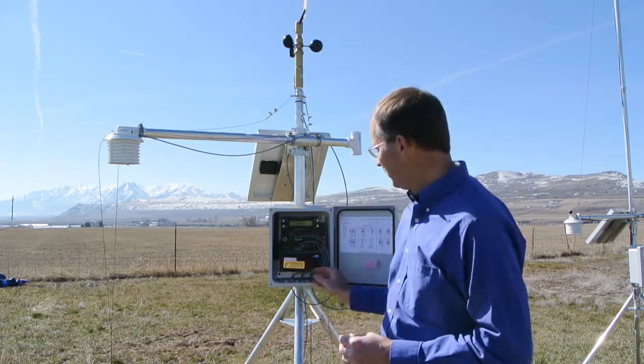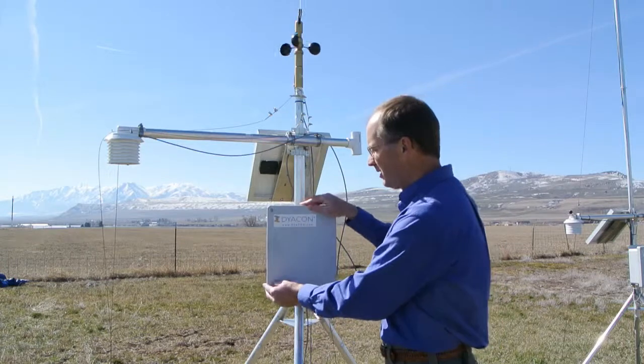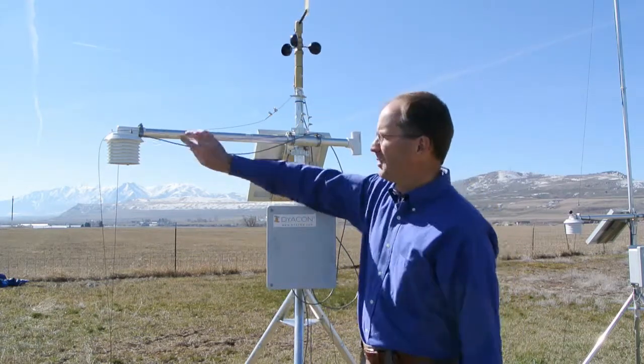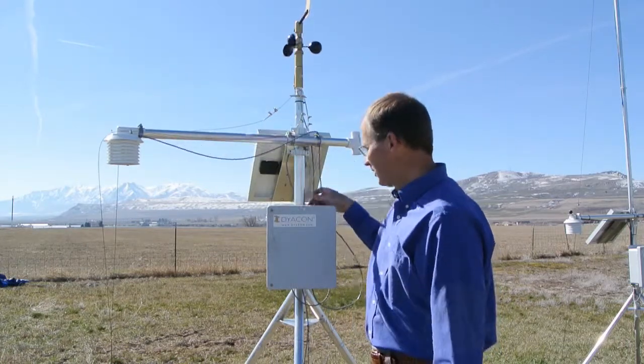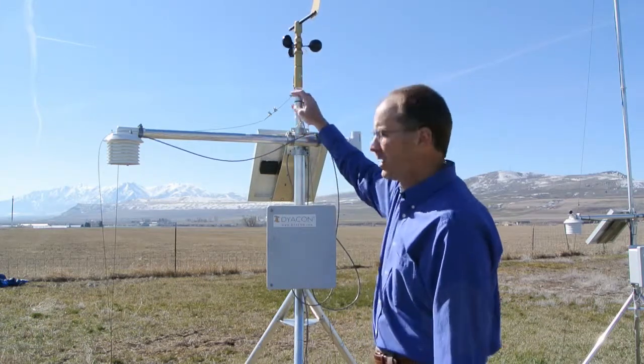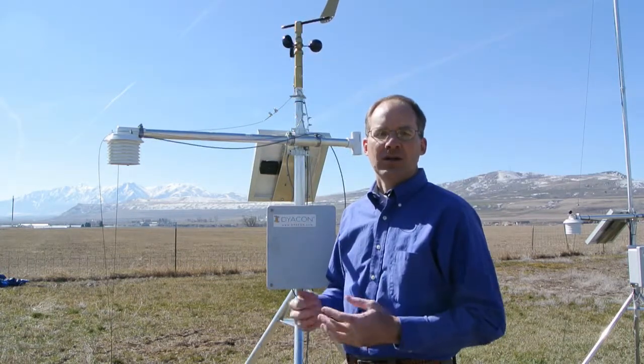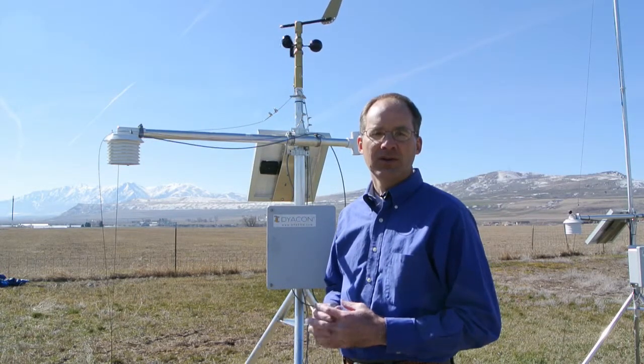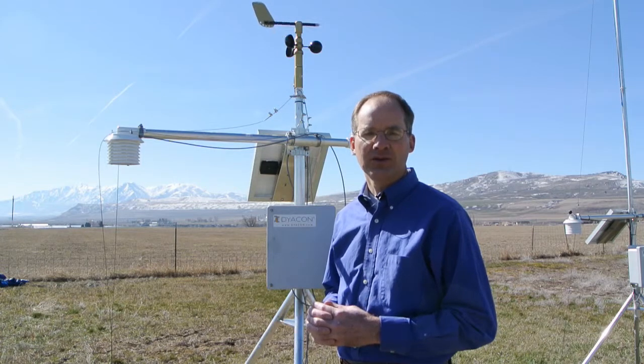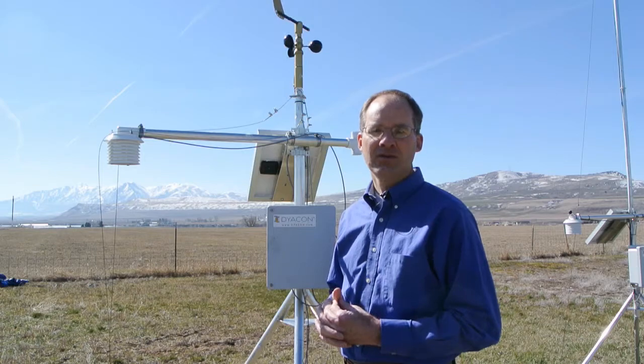With the system now fully configured and operating, we've checked the operation on the LCD. We can push the cables into the side and screw the unit closed. The next step will be to add cable ties and strain relief to all of the cables. In this case, we're using a Dyacon tripod and the mast would need to be elevated to its full position. Thank you for watching this video on the configuration of the MS-130 weather station. This is a basic sensor complement of all the pre-configured weather stations from Dyacon. If you have any questions, please give us a call or send us an email using the information on our website.